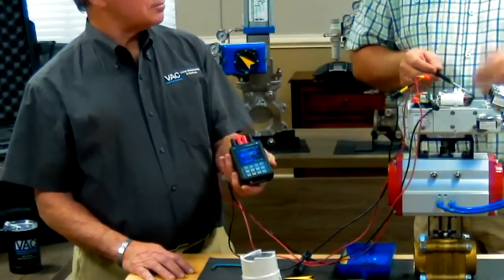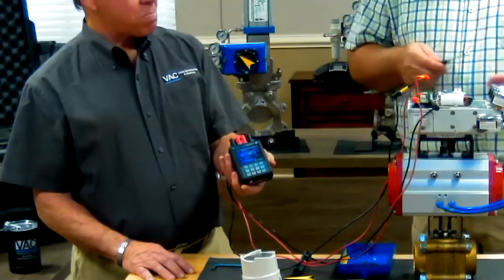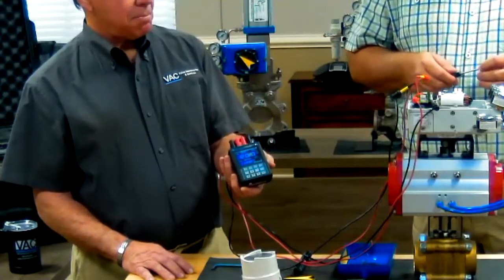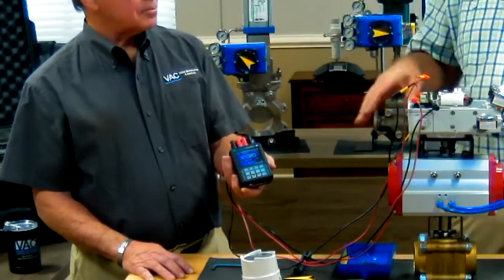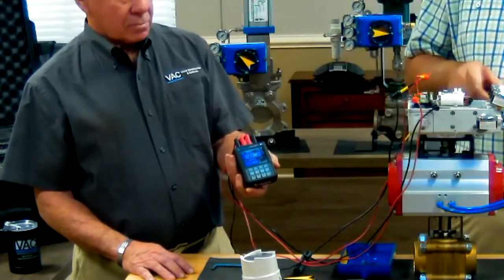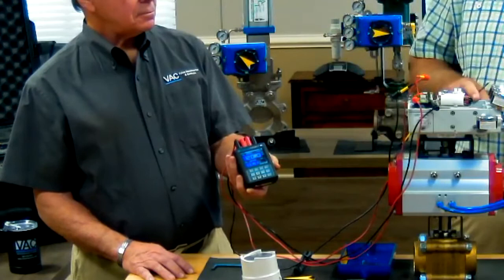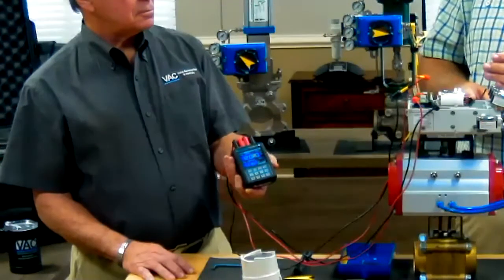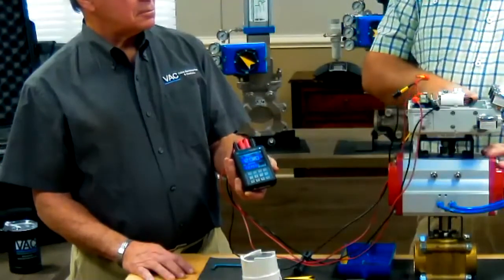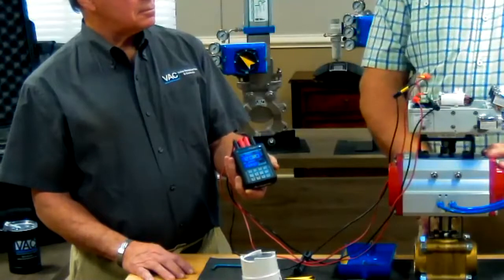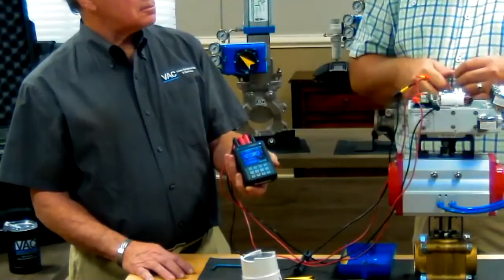Actually, this one will probably move in a little less than that. Your package may vary depending on how much friction it has in it. The ability to do this shows the customer the quality of the product - not just the positioner, but the actual assembly. So a quality positioner, in order to turn the valve, needs a quality actuator, and the valve needs to have low enough friction to be suitable for use as a control valve.